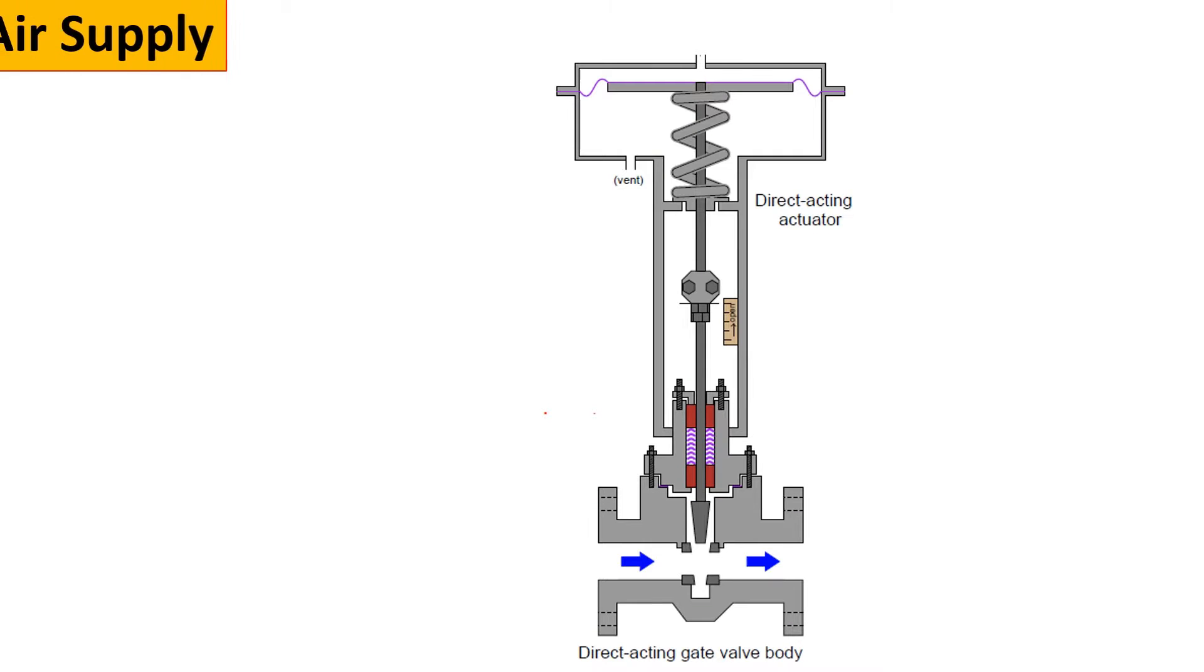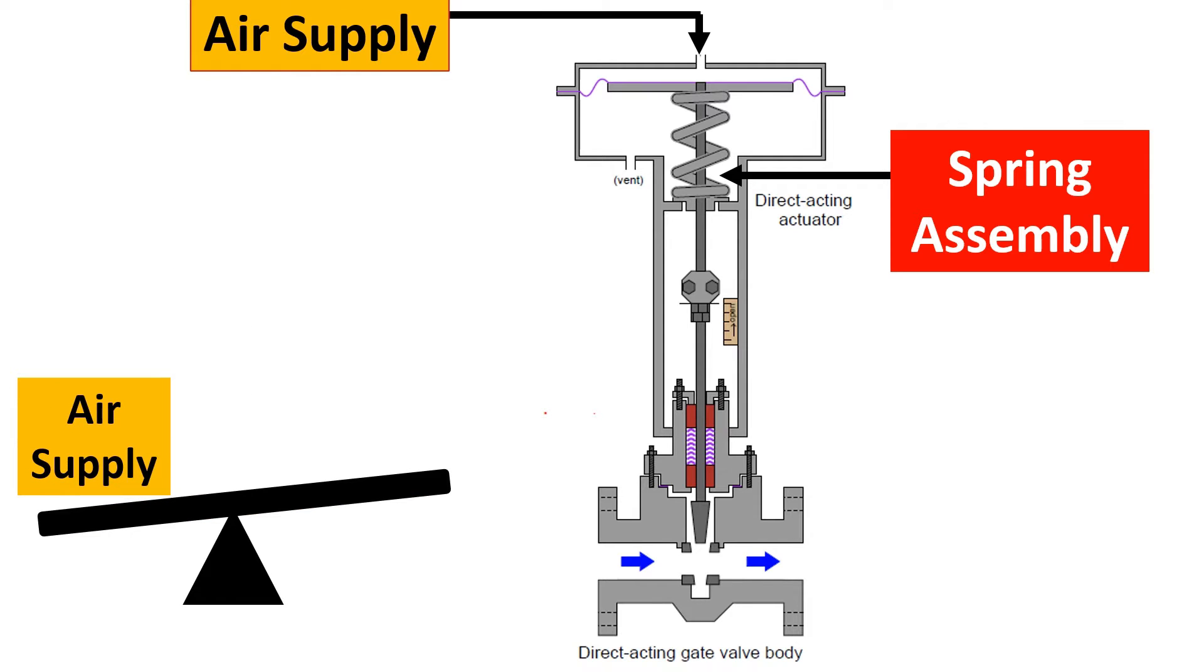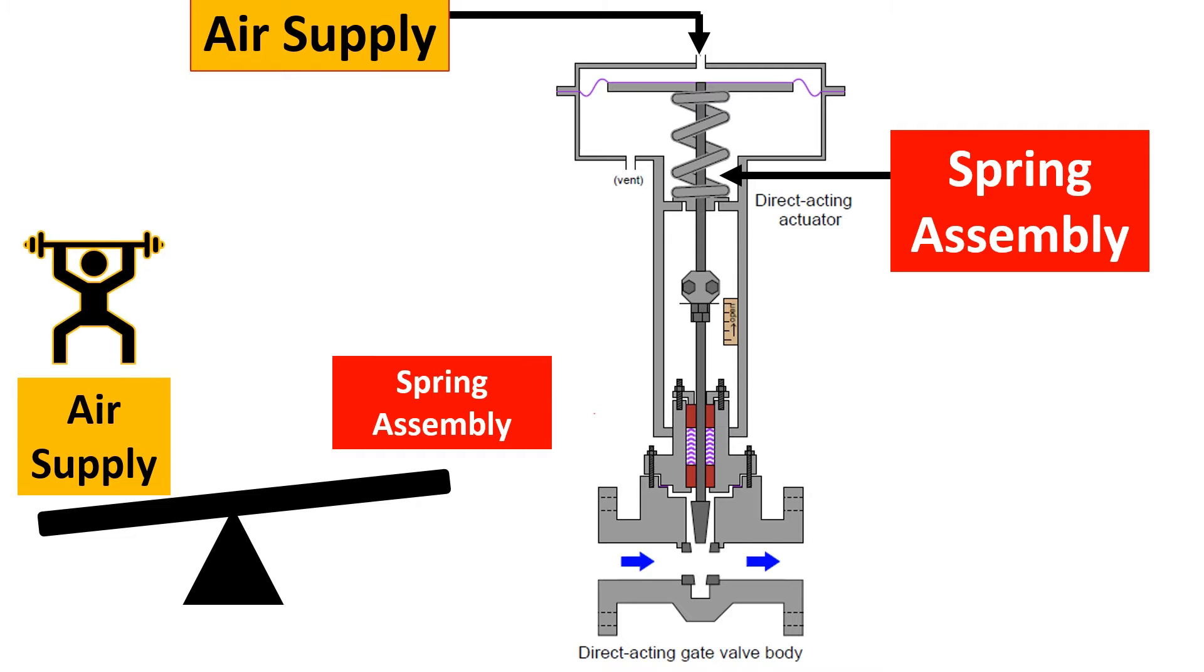So the air supply design is something where you have to see that if the air, this is a direct acting actuator and a direct acting valve. So here when you give an air supply what is resisting the air supply, it is the spring assembly. Now imagine this to be like a seesaw. Here the air supply has to overcome the friction of the spring assembly in order for the valve to function.